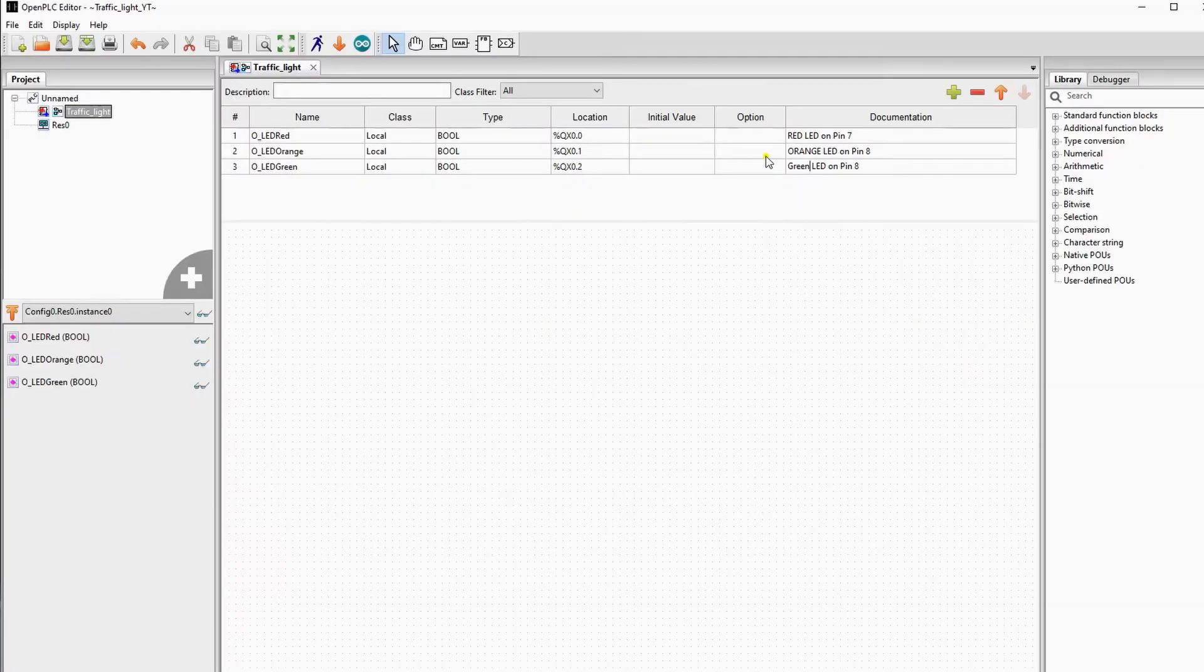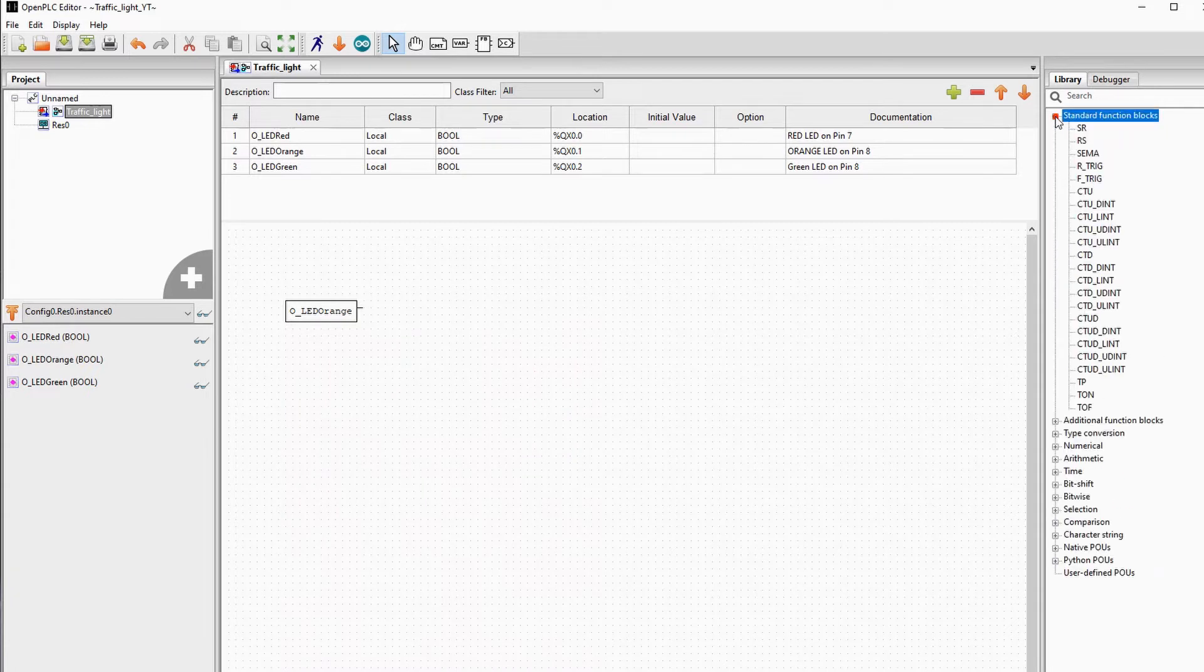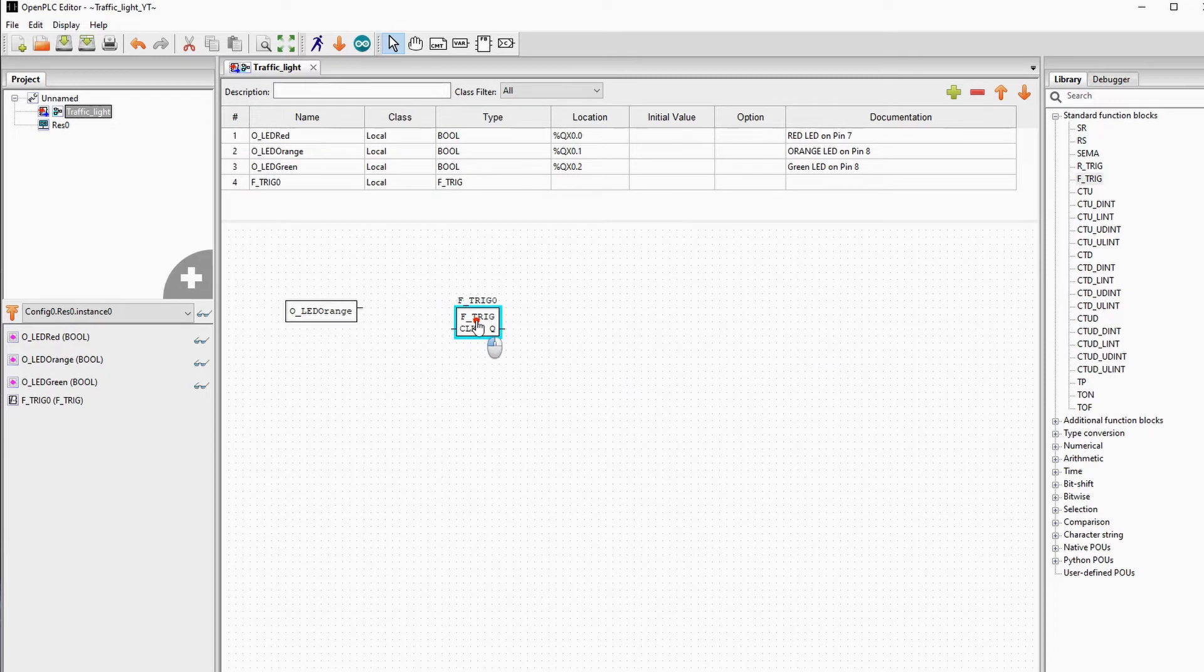After we declare the variables, we will start programming. Working with OpenPLC, I found out that in the first cycle, all outputs are momentary one cycle high, just a millisecond. And then they go directly to low.